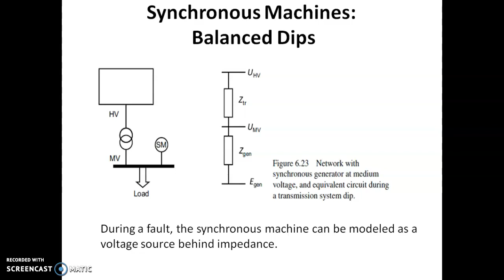During a fault, this synchronous machine can be modeled as a voltage source behind impedance. If we neglect the load influence on the voltage and the influence of the synchronous machine on the voltage at transmission level, we get the model on the right to calculate the voltage experienced by the end customers. The residual voltage found from this model is UMV equals Z generation divided by Z generation plus ZTR, times UHV, plus ZTR divided by Z generation plus ZTR, times E generation. By this model we get the residual voltage.